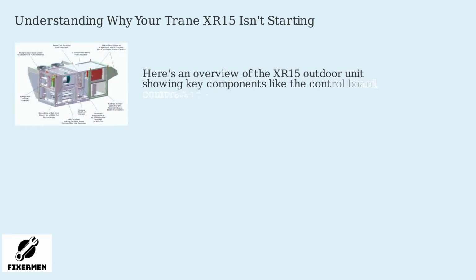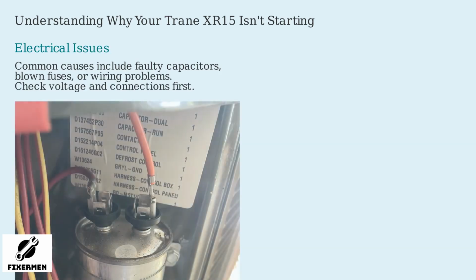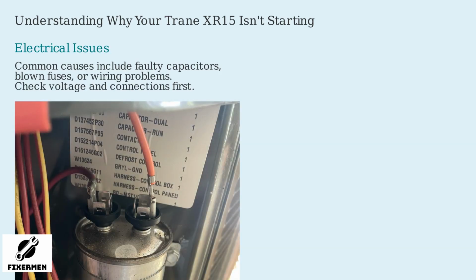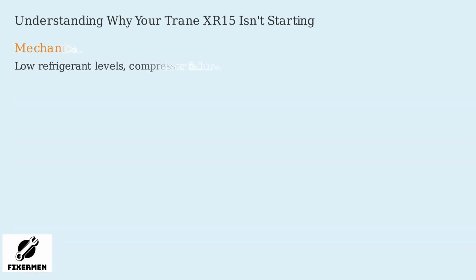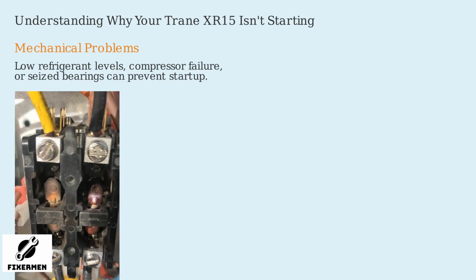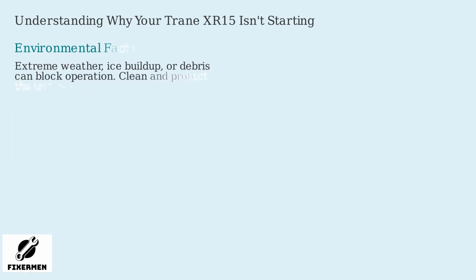Here's an overview of the XR15 outdoor unit showing key components like the control board, compressor, and fan. Common electrical issues include faulty capacitors, blown fuses, or wiring problems. Check voltage and connections first. Mechanical problems like low refrigerant levels, compressor failure, or seized bearings can prevent the unit from starting. Environmental factors like extreme weather, ice buildup, or debris can also prevent startup. Clean and protect the unit regularly.